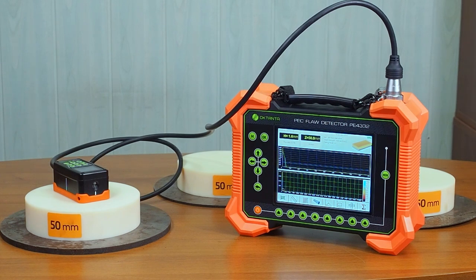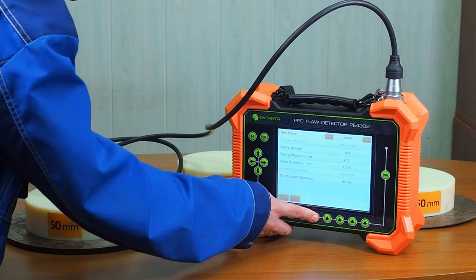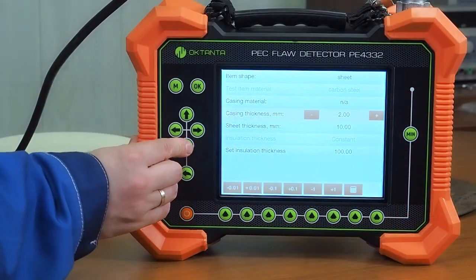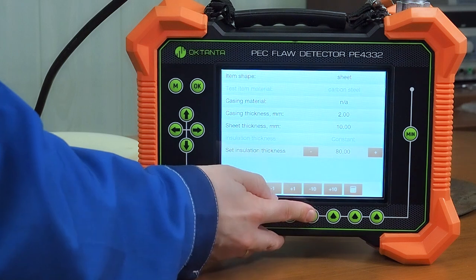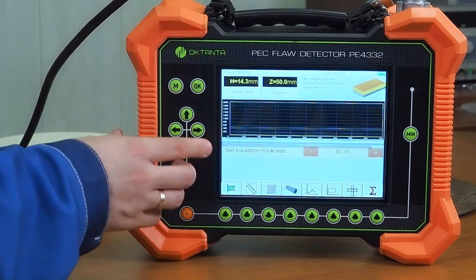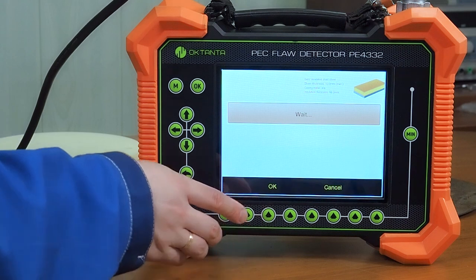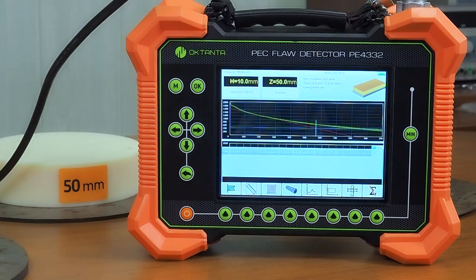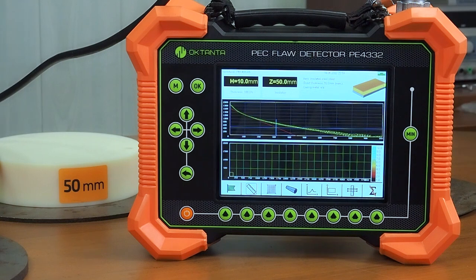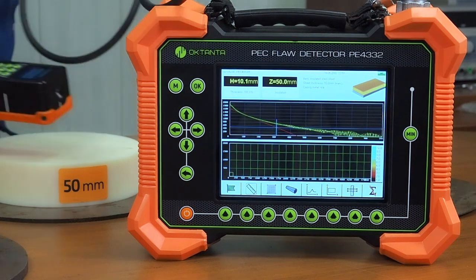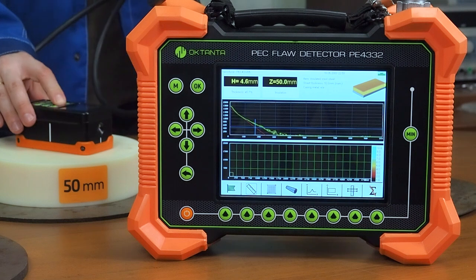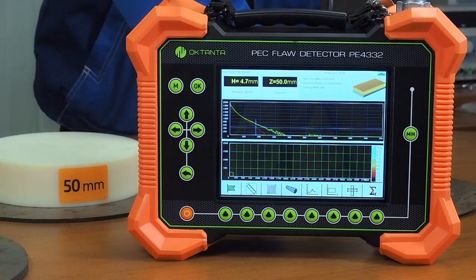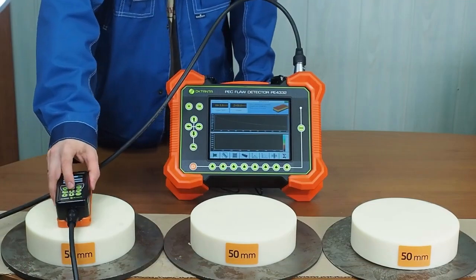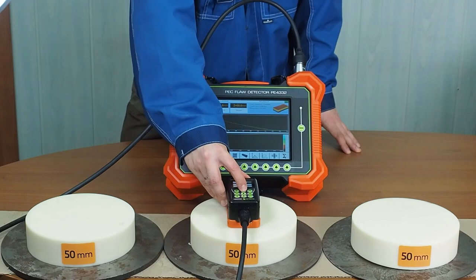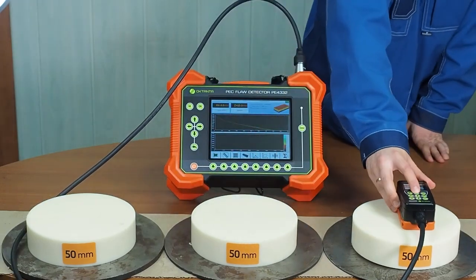Before taking the measurements, it is important to set the parameters of the test object and to carry out a quick calibration. The calibration must be carried out on each new test object. In addition, we recommend to carry out calibration when there is a clear change in the physical parameters of the test object, for example, a visible change in the thickness of the insulation. Let's carry out a calibration measurement where the metal thickness is known. When changing the sensor, we also recommend to carry out a one-time calibration away from the metal objects, for example, by raising the sensor by at least 50 centimeters above the pipe. The calibration is completed and we move on to measuring the thickness of the discs under the insulation models.